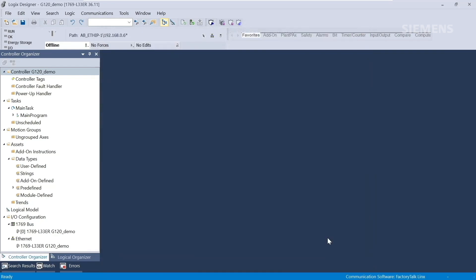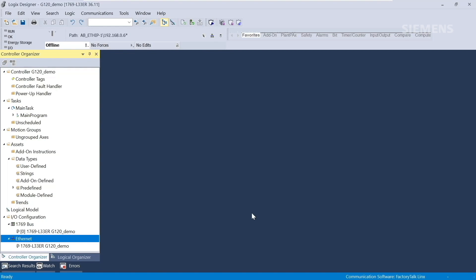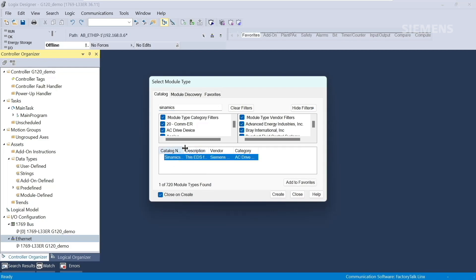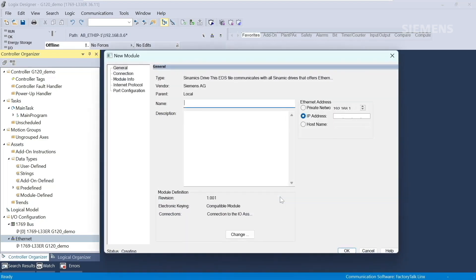Now we'll add the Sinamics G120 drive to the project. The EDS file you just registered allows us to easily add a Sinamics drive to the project tree. Under I/O Configuration, you'll click on Ethernet, New Module, enter Sinamics and select Sinamics Drive and click Create. You can name this drive whatever you want. We'll call it G120 and we'll give it an IP address. This needs to match what we assigned to the drive: 192.168.0.3.